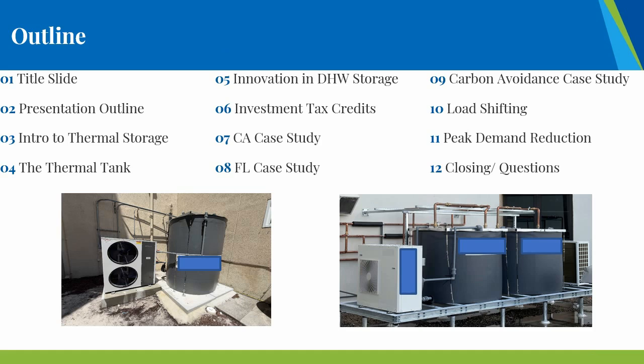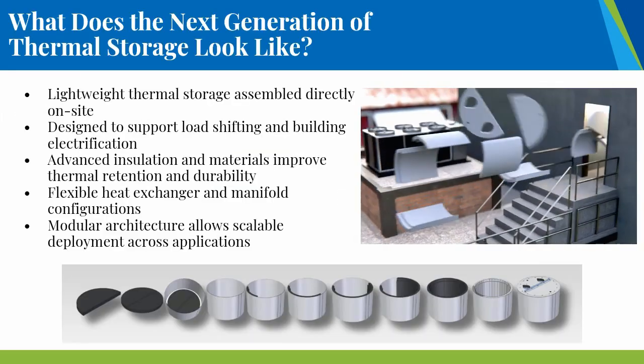But to outline what we've done in the past few years: with that base installation in the Caribbean, we asked what we could do to provide domestic hot water utilizing our energy storage tank. So using air source heat pumps and immersive heat exchangers - some unique for RO water where it's not treated, all plastic polymeric, and/or corrugated stainless steel loop heat exchangers, or pumped suction tube and diffuser assemblies - we've put up several installations around the country. In this outline, we're looking at the tax credits that will end up supporting those installations.